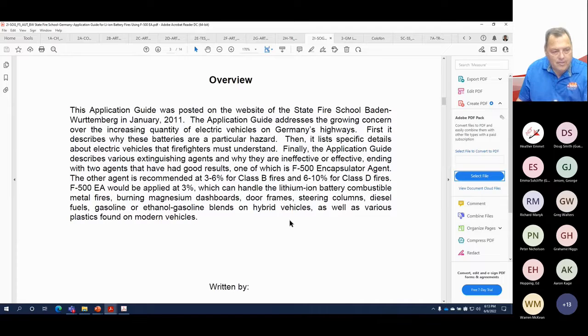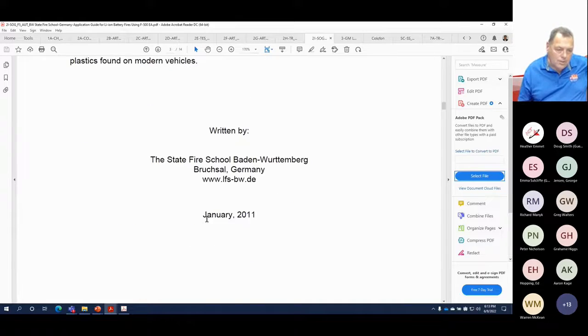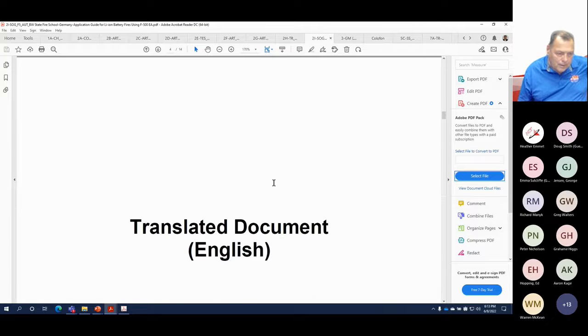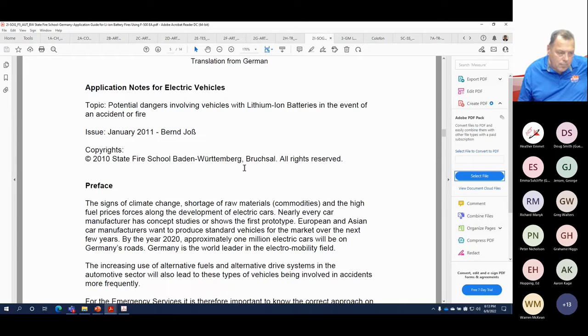So this just discusses the fact that they did the test, and F500s were recommended at 3%, 6%, and for Class D, 3% would handle lithium-ion batteries, metal fires, burning magnesium dashboards, door frames, steering columns, diesel fuel, gas, ethanol. So this was an article that was written by, or I'm sorry, this is an SOG application note and guideline written by the Baden-Württemberg Fire School.